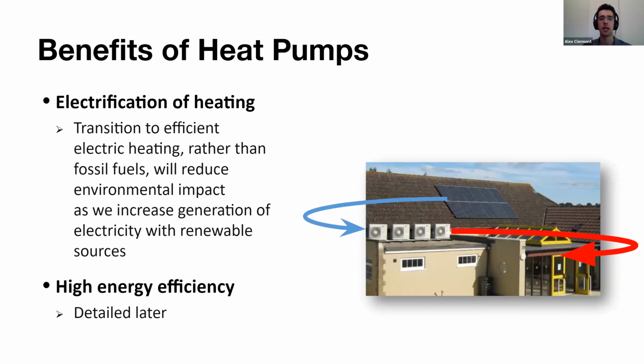So why use heat pumps? What's the main benefit? Heat pumps are used in cooling everywhere, and we're going to talk about their efficiency metrics in a little bit, but electrifying heating is really where heat pumps come into play. With electric heat, you have 1 kilowatt of heat from the grid, and that gets you 1 kilowatt of heat at your source. With a heat pump, you can move 2 to 5 units of heat from outdoors to indoors. And if you're using electricity, you can now use clean electricity, whether that's from the grid or on-site generation.